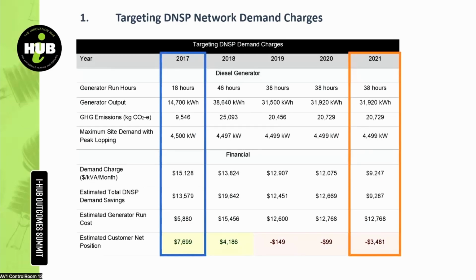The results of the modelled 5 years are shown here. So the best year was in 2017, which is highlighted in blue there. And in 2017, the generators needed to run for 18 hours to keep the site's maximum demand no greater than 4,500 kilowatts. And this resulted in an estimated demand charge savings of approximately $13,500 and a generator run cost of $6,000. So this led to a customer net position of about $7,700.